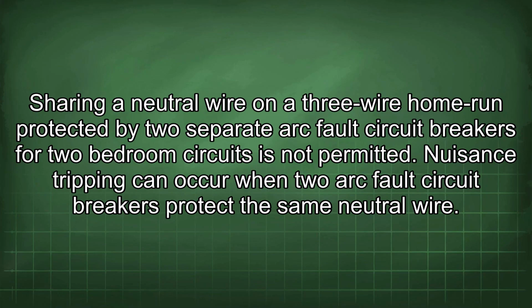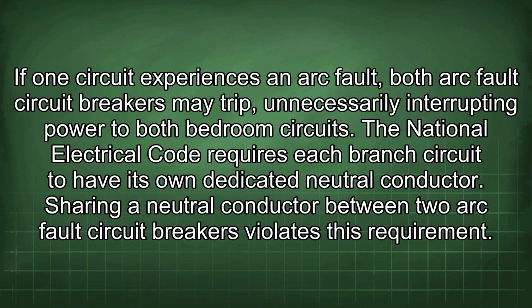Sharing a neutral wire on a 3-wire home run protected by 2 separate arc fault circuit breakers for 2-bedroom circuits is not permitted. Nuisance tripping can occur when 2 arc fault circuit breakers protect the same neutral wire. If one circuit experiences an arc fault, both arc fault circuit breakers may trip, unnecessarily interrupting power to both bedroom circuits. The National Electrical Code requires each branch circuit to have its own dedicated neutral conductor.